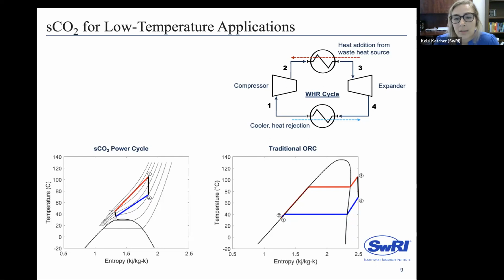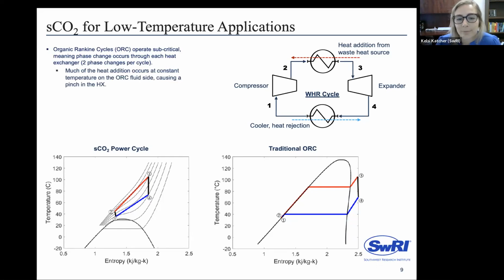One thing to note with the ORC cycles, as Tom mentioned earlier, is that you're actually phase changing through both of your heat exchangers. The Rankine part means you're subcritical and traversing the dome. So whenever you're running through your heater, following that red line, you're heating in liquid phase until you start getting into the 2-phase region and gas phase starts forming. As you traverse the dome, you're moving at constant pressure and constant temperature, just converting to a higher gas volume fraction until you reach full gas phase, and then you start gaining temperature again.